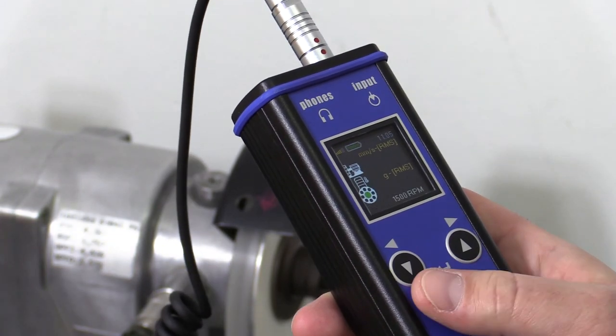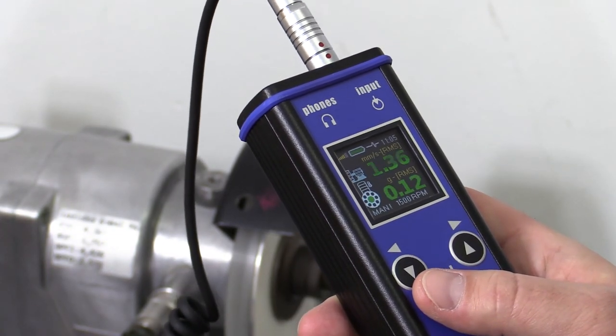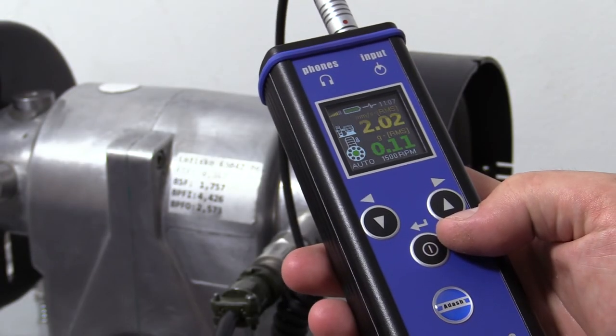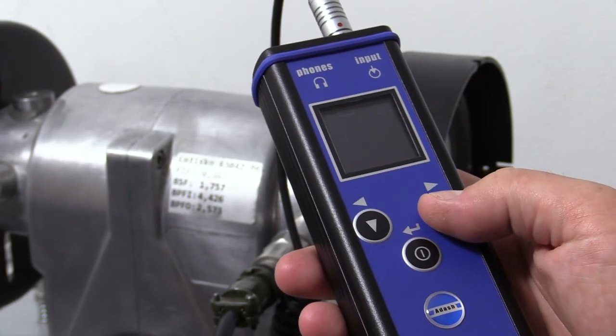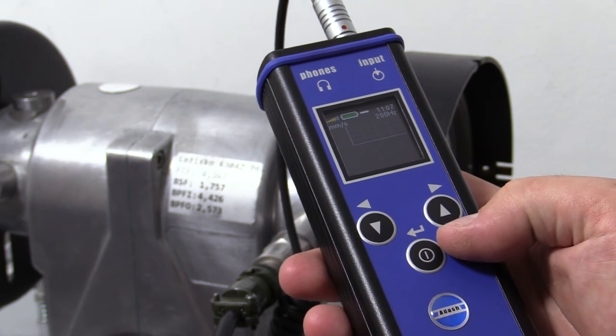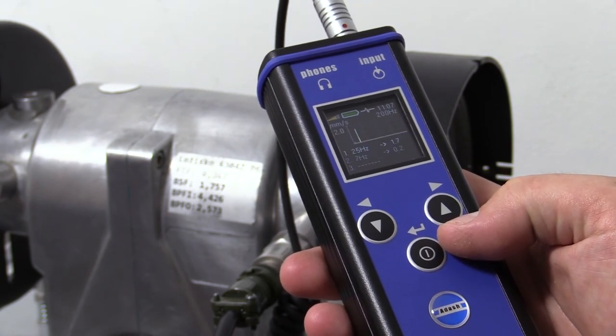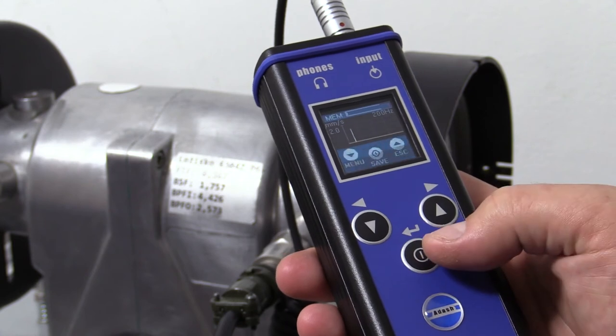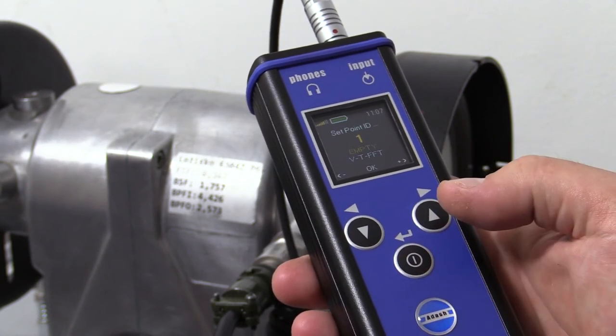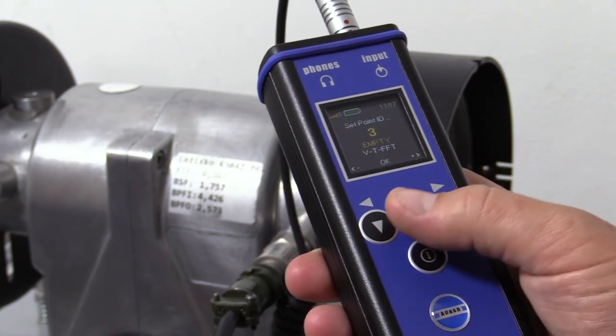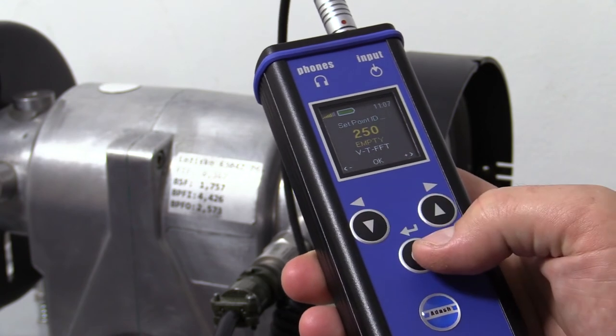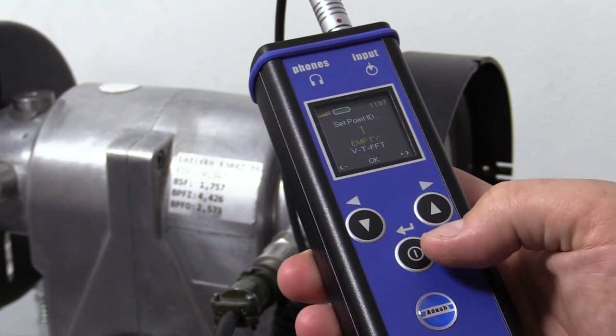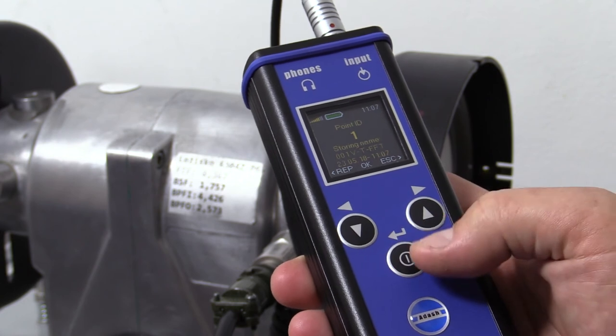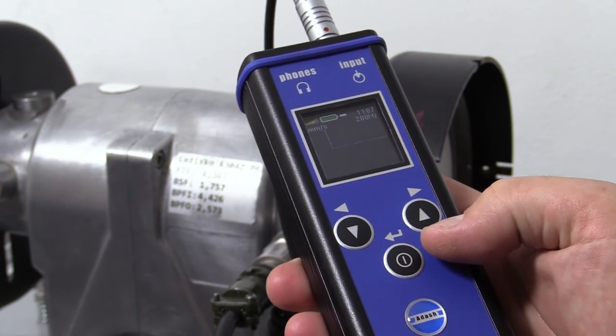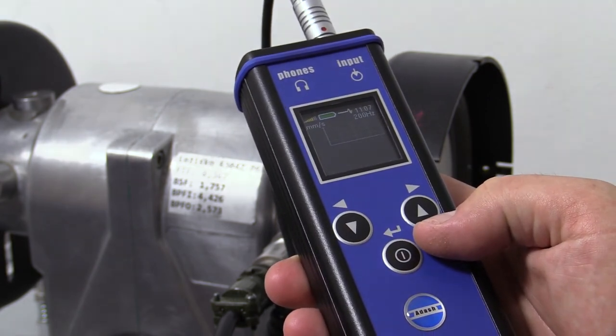We will now save also measurement which is not included in the root. This is called off-root data, as I mentioned earlier. Go to any measurement screen which you want to save. I go to this FFT screen. I press the middle button and save. The Vibrio M asks me into which memory position I want to save this measurement. There are 250 positions in the memory. I select one and confirm by OK.